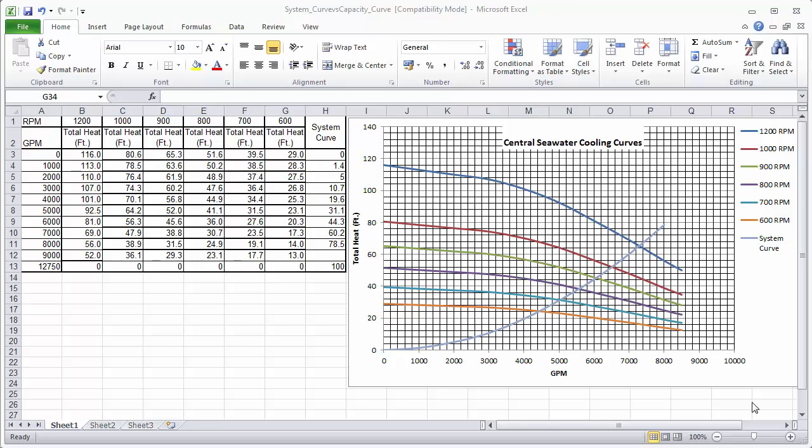The company had a set of template Excel files, one of which was used to evaluate the effect on pump performance with changes in pump speed. We were evaluating a system which had a set of centrifugal pumps. The pump capacity curve data was based on an operating speed of 1200 RPM and they needed to consider the speed of the pump at 600 RPM.